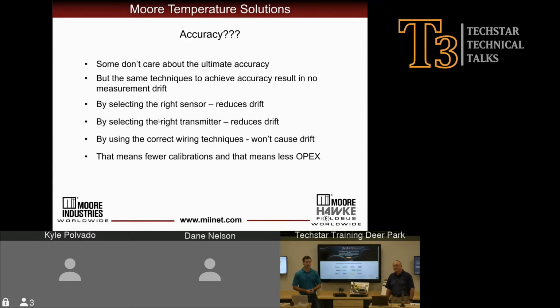So again, there's a lot of processes that we're taking the temperature of that we don't need to measure accurately. Some processes need an accurate temperature measurement, and some we're just looking for spikes or different trends over time, something that might indicate some type of failure for us. But at the end of the day, some of the same techniques that we use to achieve accuracy result in less measurement drift. So if calibrations are important to you, if a preventative maintenance schedule for your temperature sensors and transmitters is important to you, then you might implement some of these techniques as well, even though it might not be a high accuracy temperature measurement that you're trying to take.